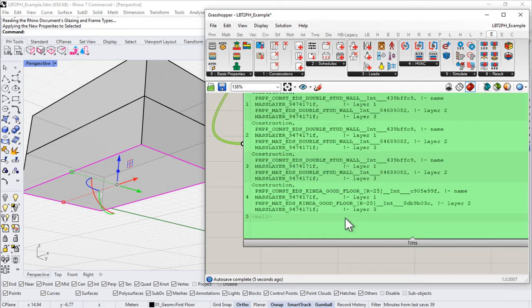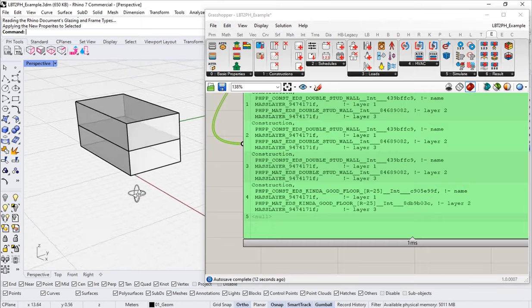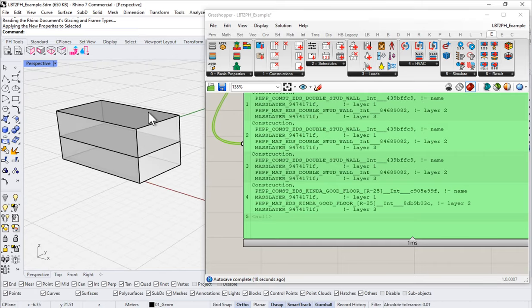Now if we push this through, notice our 'it's kind of good floor' assembly is popping up in the list. We still have that last null, but that's the ceiling assembly — we don't need to assign anything there; that's not a heat loss surface. If we were going to do an EnergyPlus model simultaneously we'd want an actual construction there, but the default construction for those interstitial spaces is going to be fine in most cases.